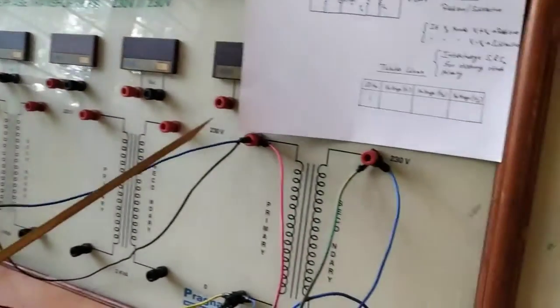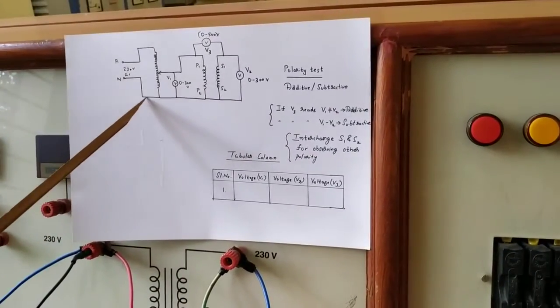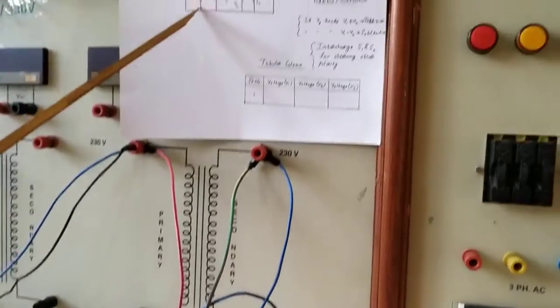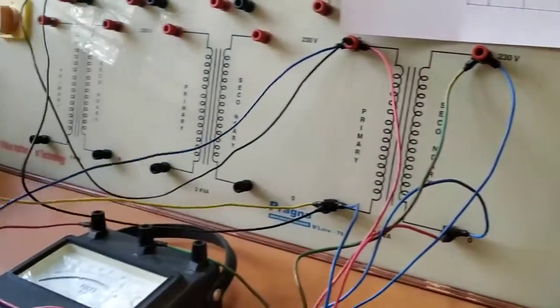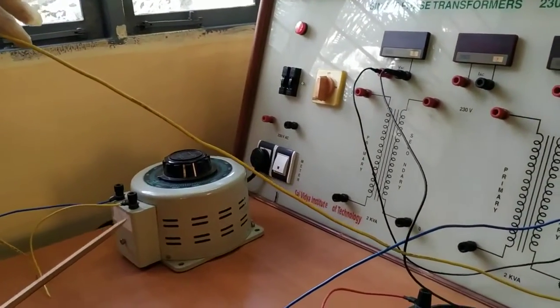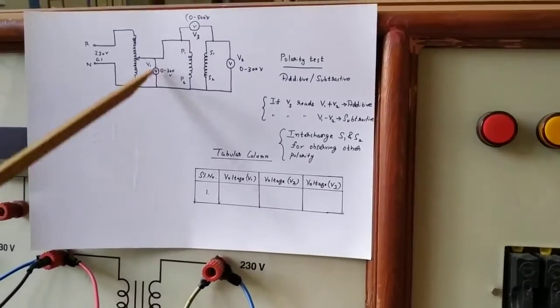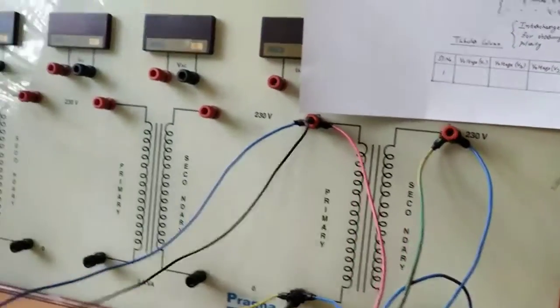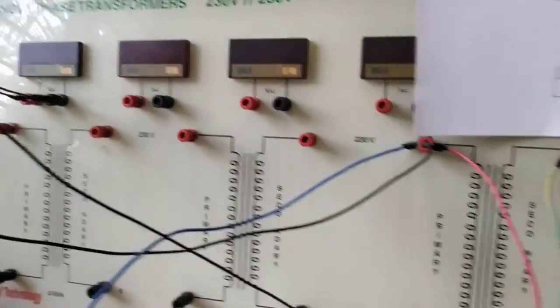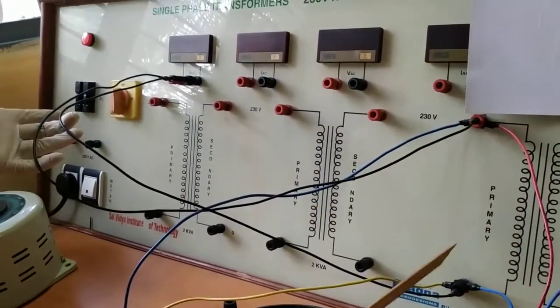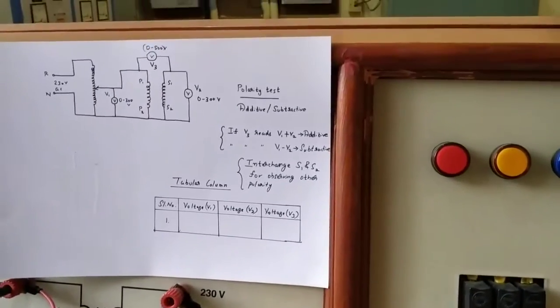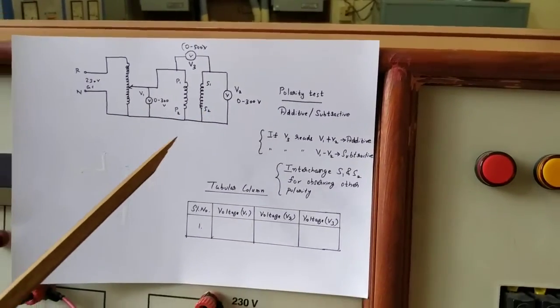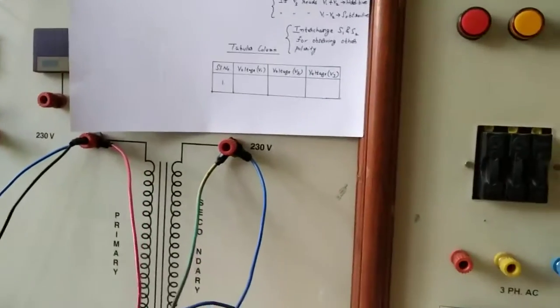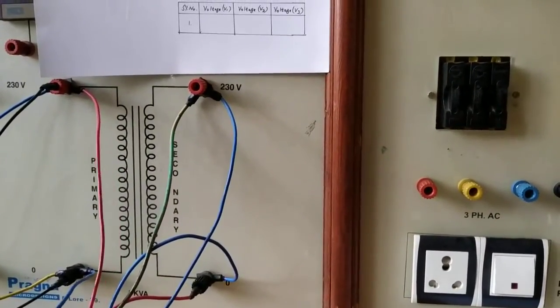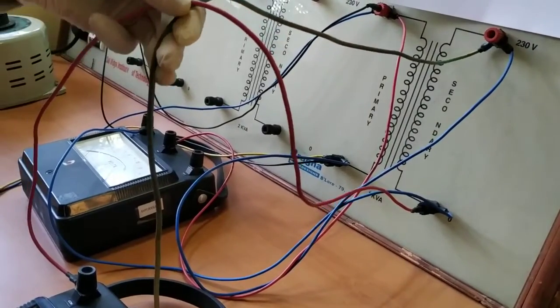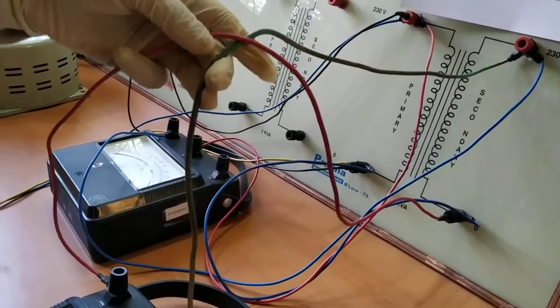From the transformer it is going to P1. P2 is getting connected back to the neutral, that is, to the other end of the auto transformer. We have a panel voltmeter connected across P1 and P2. Then across the secondary S1 and S2 we have another voltmeter. Let us see the connection here. Across the secondary we have another voltmeter connected, as we have seen in the circuit diagram.